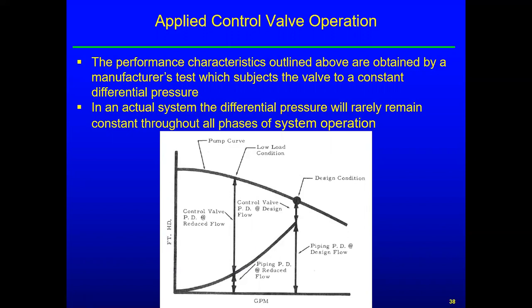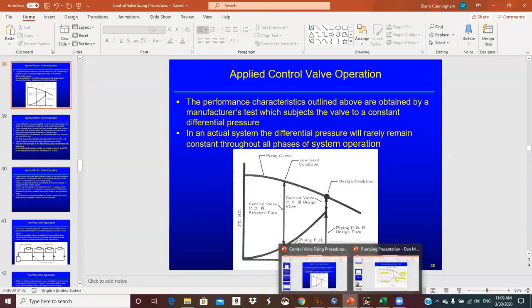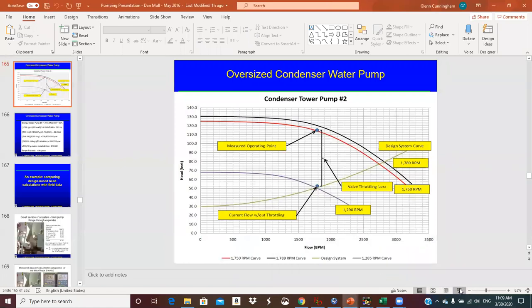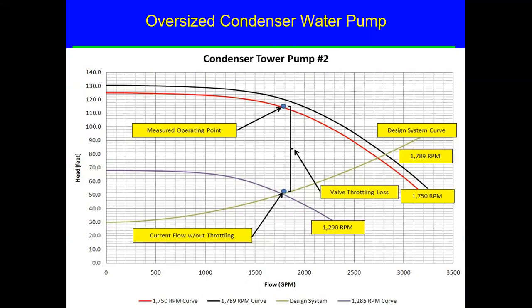And now to illustrate that, I'm going to get out of this presentation and go to a presentation I actually use in 4260, but these courses all kind of overlap a little bit. So I know we've got a lot going on here, but this is a condenser tower, or cooling tower pump. It is number 2 at some plant that I went to. But basically what we're showing here is an operating point, a measured operating point up here at the top of the curve, which looks like about 116 feet of head. And the flow rate is a little short of 1800 GPM, maybe 1780, 1790, something like that. Okay. And so this is where we're operating.